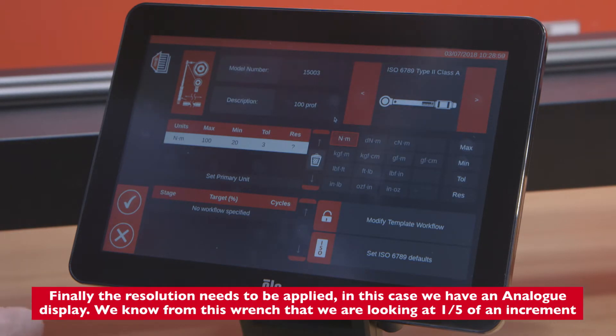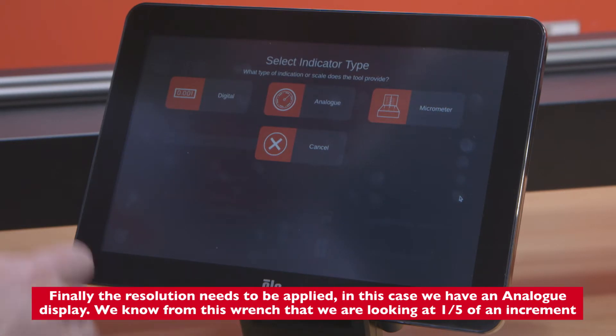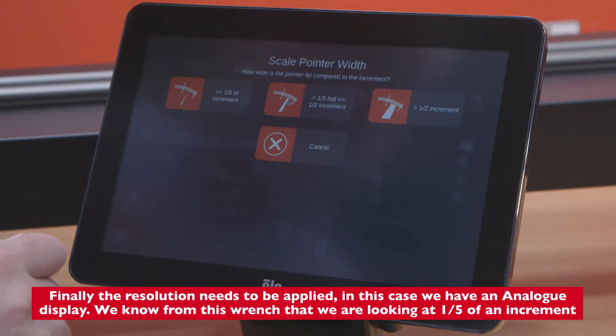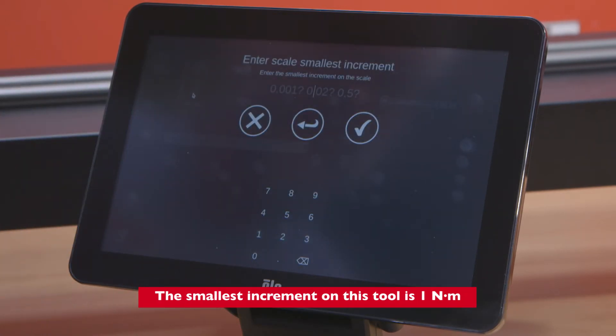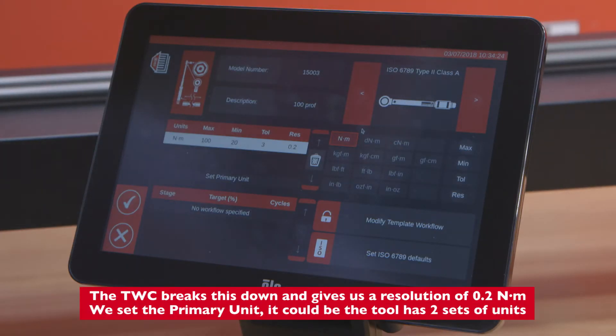Finally, the resolution needs to be applied. In this case we have an analog display, and we know from this wrench that we're looking at one-fifth of an increment. The smallest increment on this tool is 1 Newton meter, so the TWC breaks this down and gives us a resolution of 0.2 Newton meters.